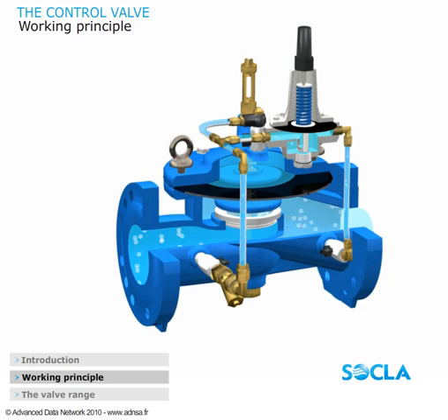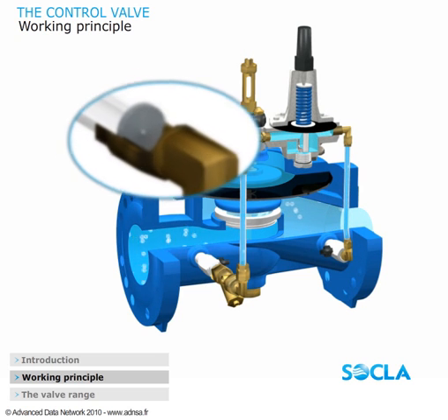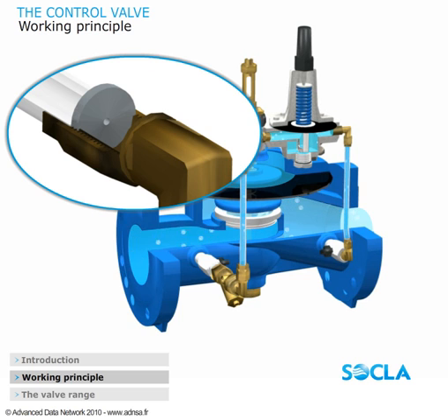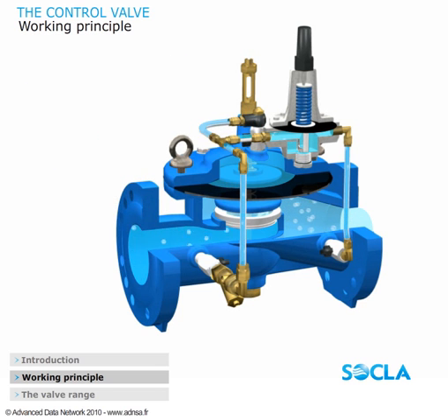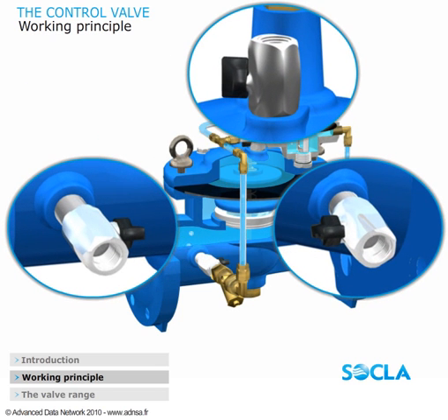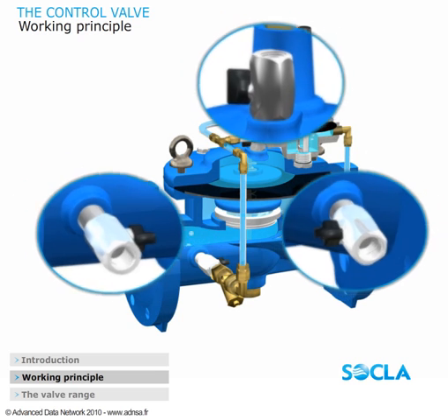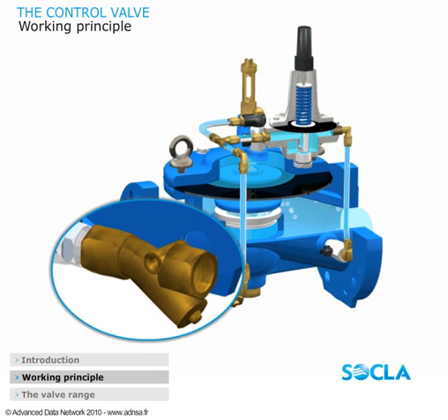A variety of accessories complete the pilot circuit. An orifice. This gives priority to evacuating the pressure above the membrane of the main valve. Isolating valves. These assist with maintenance. And a strainer, which protects the pilot circuit.